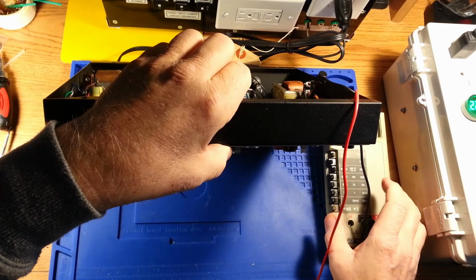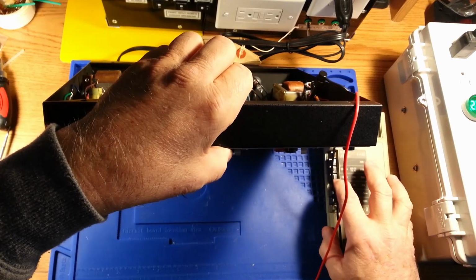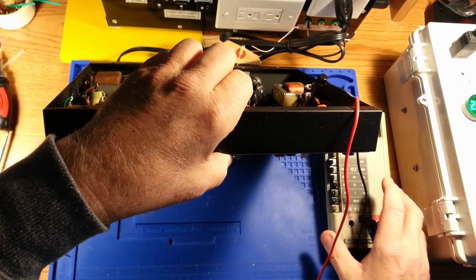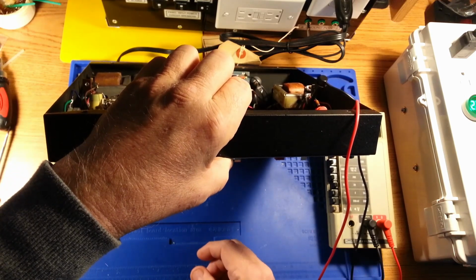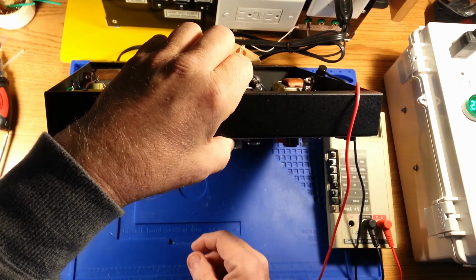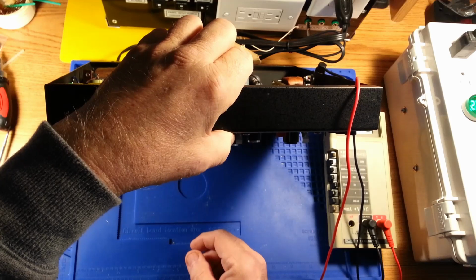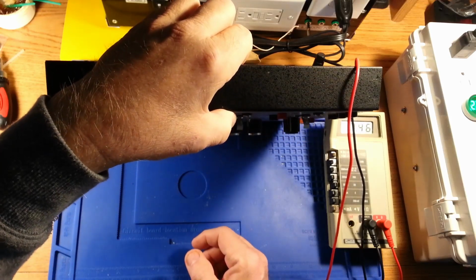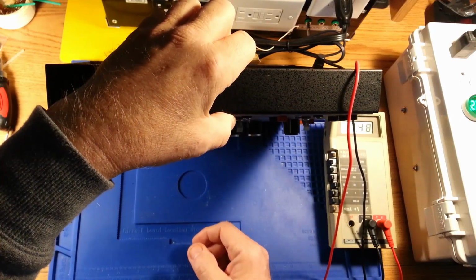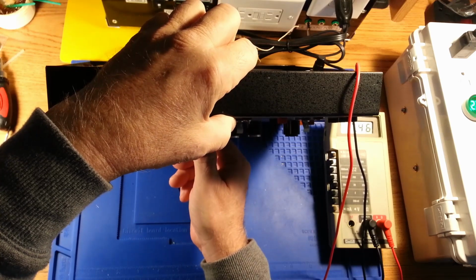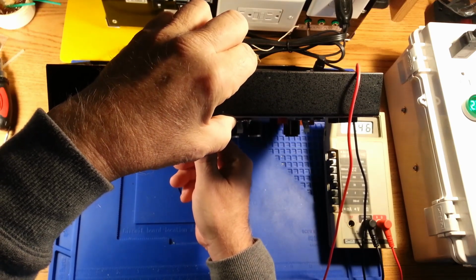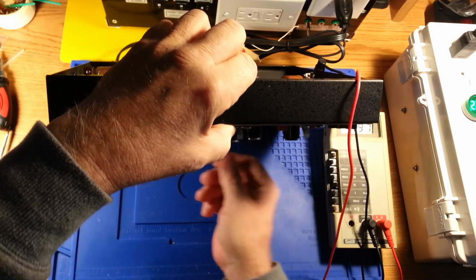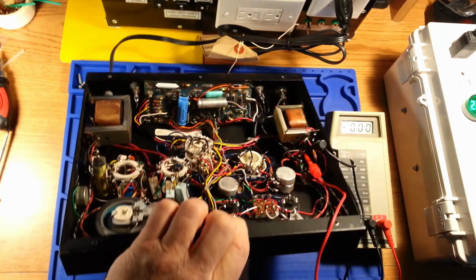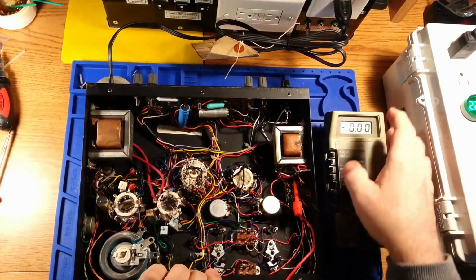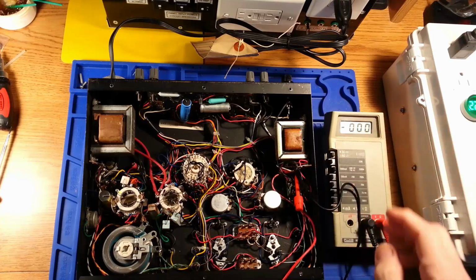We are down to 7.45 volts AC on that transformer. That transformer only works when the majority of the function settings are in anything but the reverse voltage setting. So at this point, I'm going to turn the unit off. I'm going to try to set up to read the high voltage transformer output.